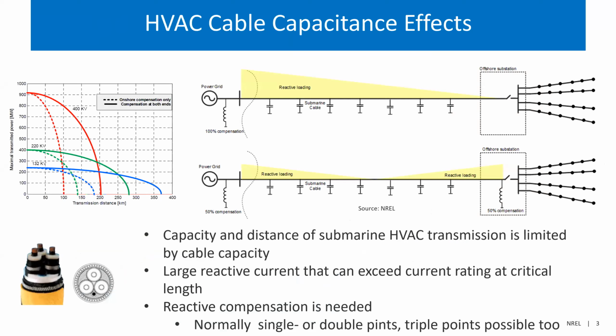It's mainly because of the capacitance of the cable, which in turn is because of the armored shield that is normally around these buried XLPE cables used as export lines in offshore wind power plants. After a certain distance, the charging current in this capacitance becomes so high that it essentially consumes the whole current rating of the cable, so you cannot push any more current through this transmission. And for a high voltage, you can achieve higher power capacity, but what you lose is essentially distance.